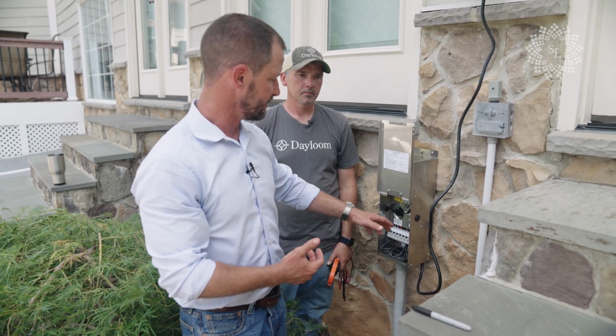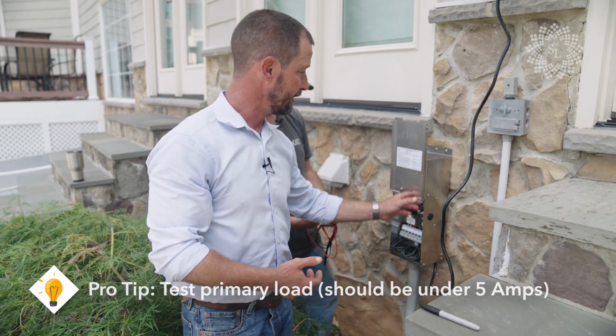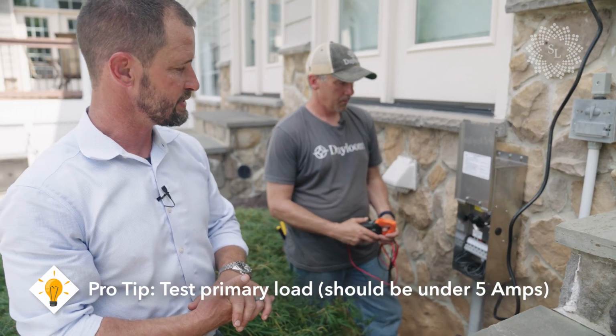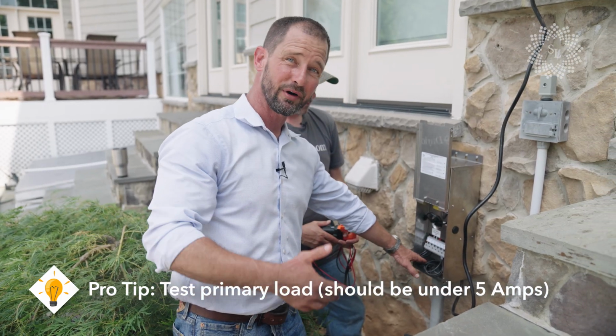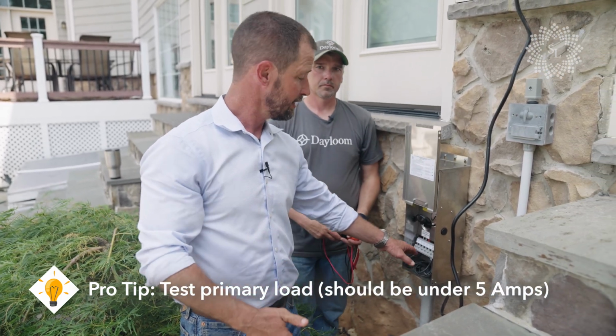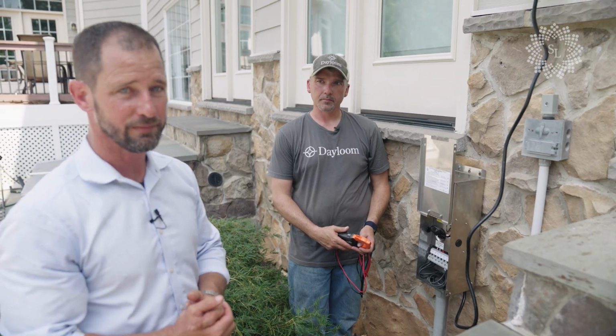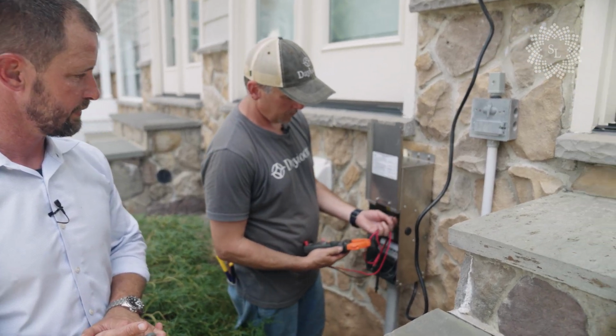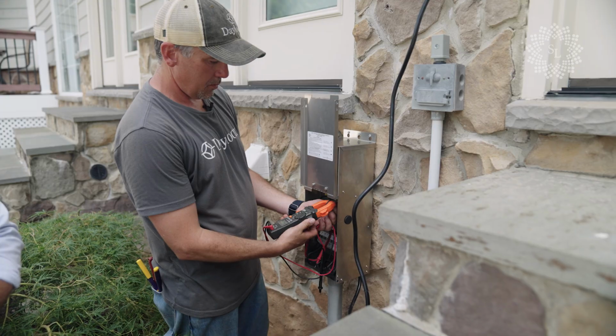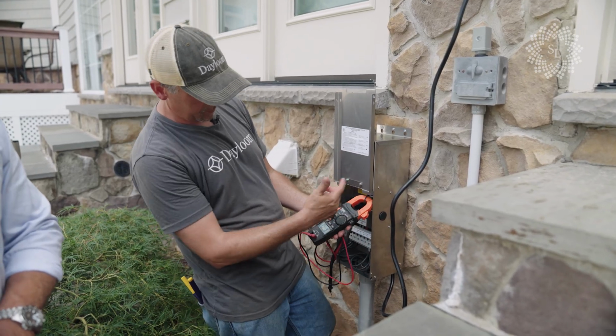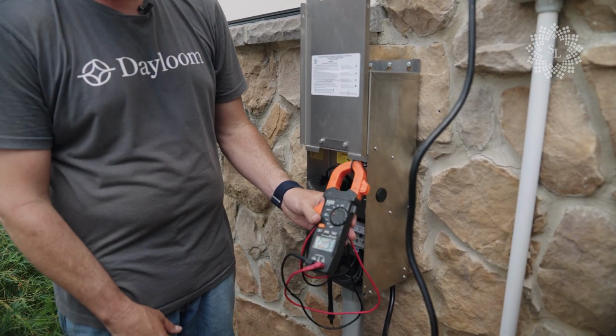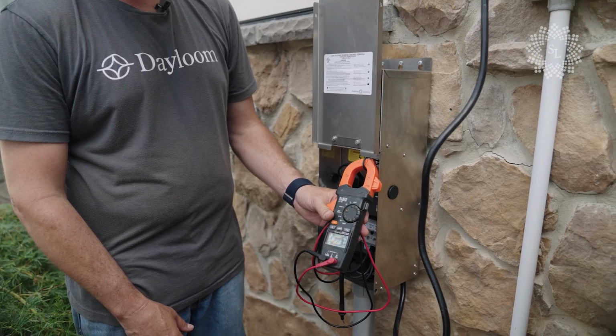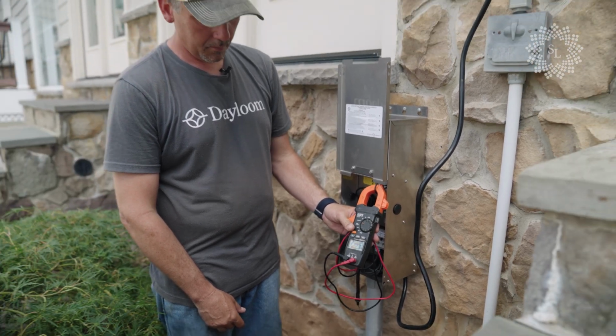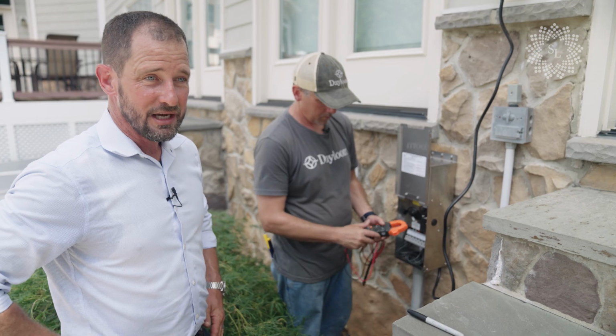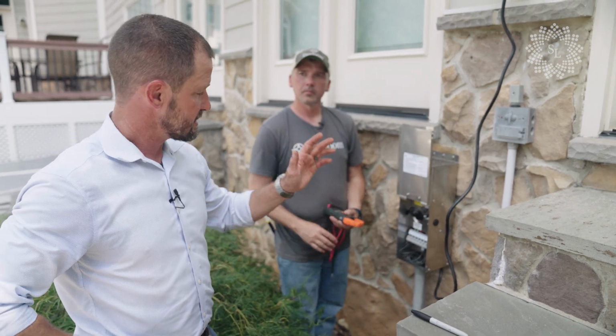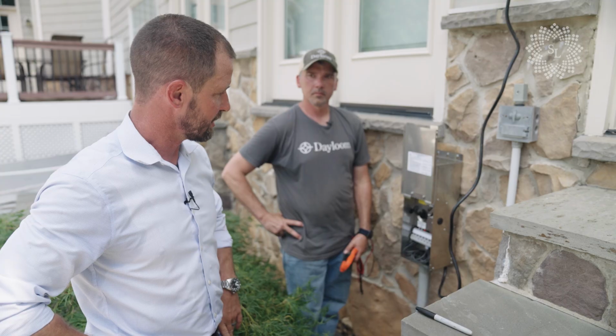The second thing that's important to test is your primary. This transformer can hold 5 amps. So sometimes you could have this running perfect where both sides are under 20, but then you go to test the primary and the primary is over. So Josh, go ahead and show how to do that. You may not have known what that loop was for. Put it around the photocell loop right there. And we're at 2.23 total amperage on a 5 amp transformer. So everything's testing out perfect. We got good voltage to each of the lines. We have good amperage. This is going to run nice and cool.